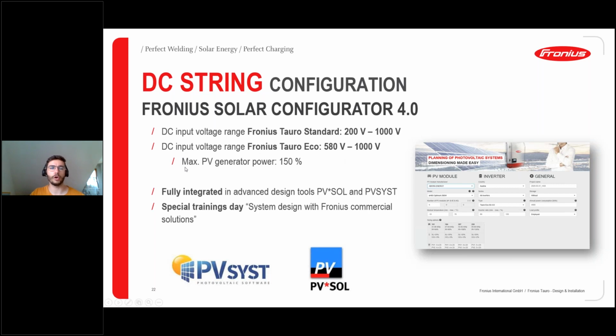What we also have on all of our products is an oversizing possibility. The PV generator can be oversized to 150%, so on a 50 kilowatt device we can mount 75 kilowatt peak without any problem. The only things we need to make sure of are not exceeding the 1000 volts, and not exceeding the maximum current of the MPP tracker and the strings themselves.